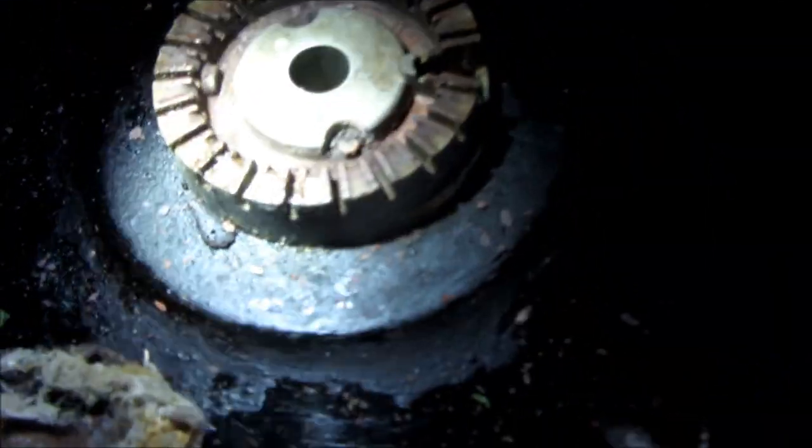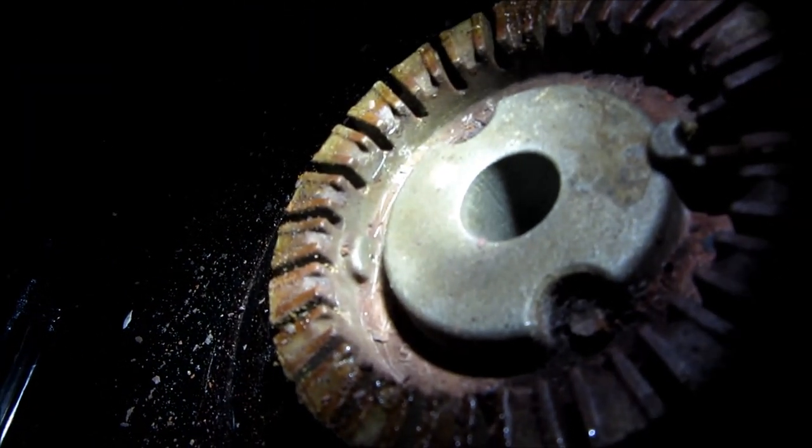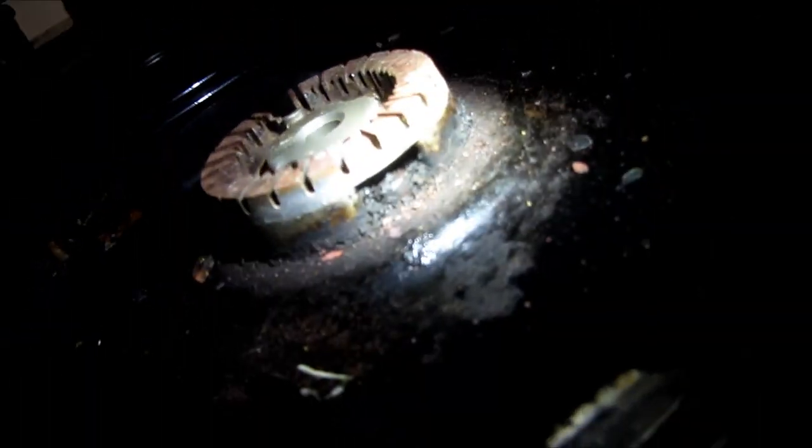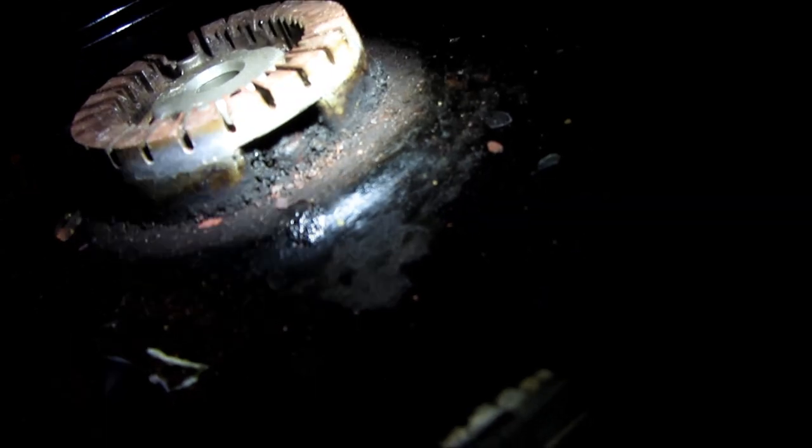I smell gas because it's not lighting. There's a little hole right there and those little holes have a small jet in them and those jets all have to be cleaned out. And that jet goes right down to that electrode. That one's pretty dirty, that one needs to be cleaned.